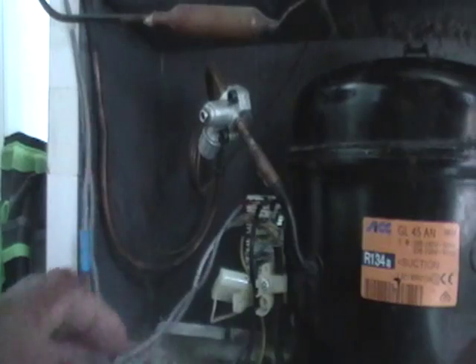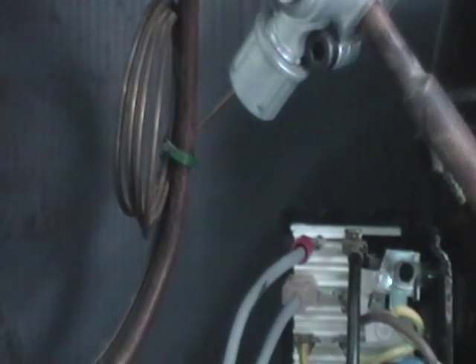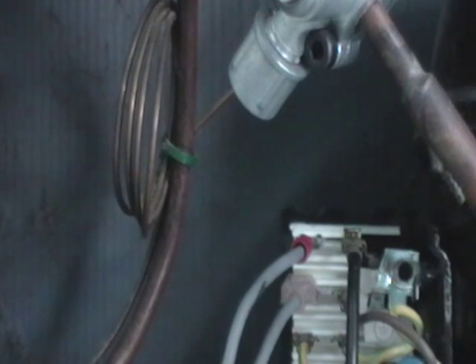One will go to the compressor. As you can see, the one on top goes to the common terminal of the compressor, which is hooked up to a thermal overload. So this is common, it goes to the overload, and all that happens is it breaks electrical flow here, opening and causing electricity to stop flowing to common, which shuts down the compressor. That's all that happens here, really and truly - no big deal.